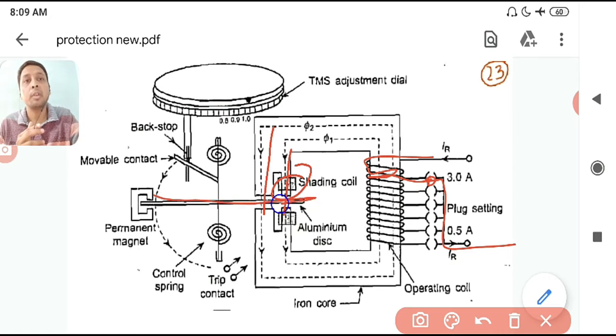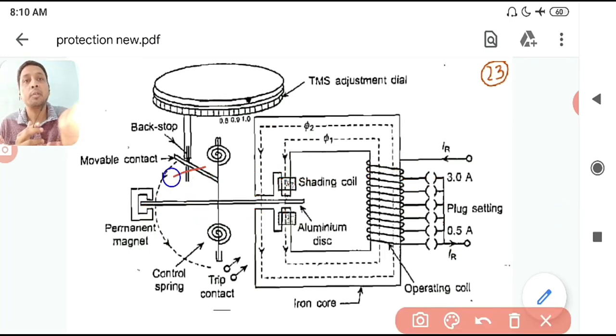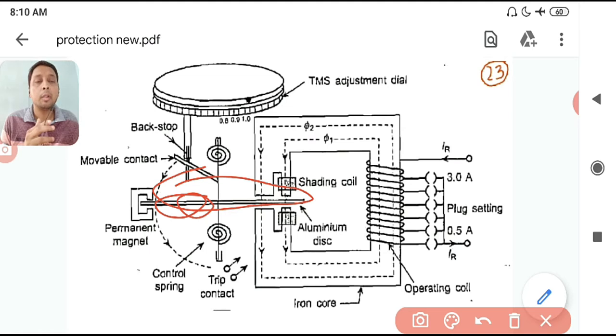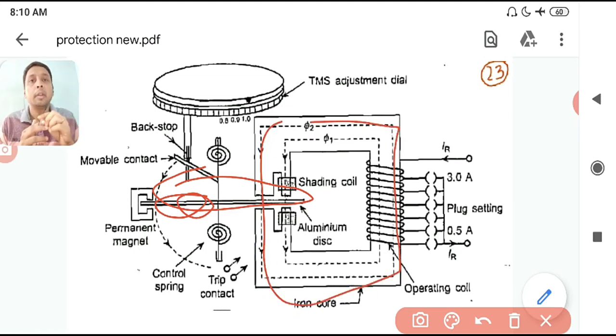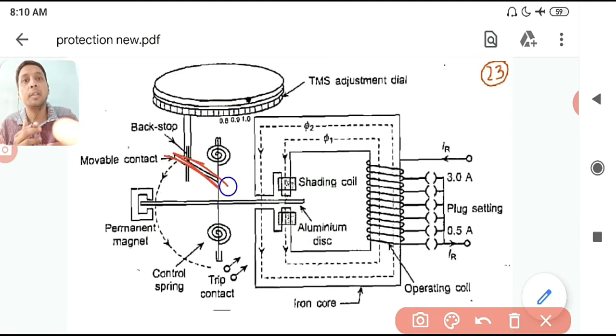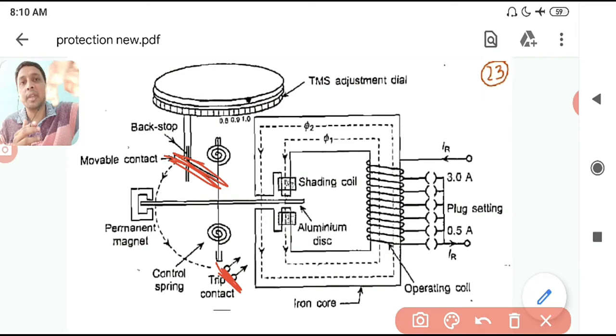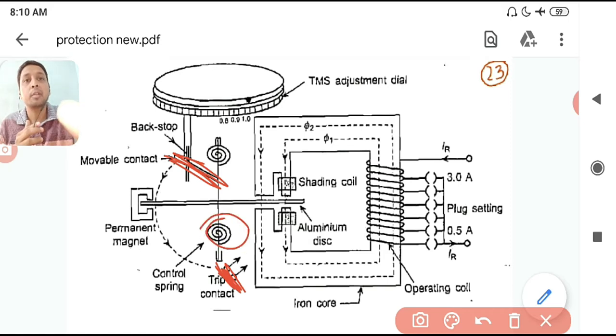This is the aluminium disc that is rotating. You can see the disc in the figure. Next are the trip contacts — if this movable contact touches the fixed contact, the trip circuit is short-circuited. The disc rotates, and once it comes there it touches that contact, getting shorted, and the trip signal is given.